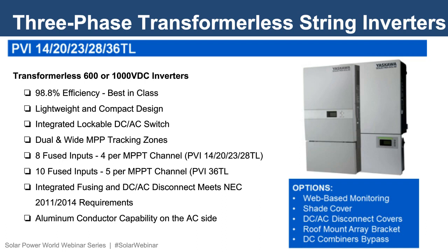Solectria provides a wide range of three-phase transformerless string inverters. A lot of flexibility, perfect for commercial, industrial, rooftop projects. These units come in a variety of power classes: 14, 20, 23, 28, and 36 kilowatt machines. The 14 and 20 kilowatt inverters are designed for 600 volt DC arrays, while the 23, 28, and 36 are designed to be used with 1000 volt DC systems. The 14 kilowatt machine has a 208 AC output, while the 20 through 36 are designed for 480 volt connections.